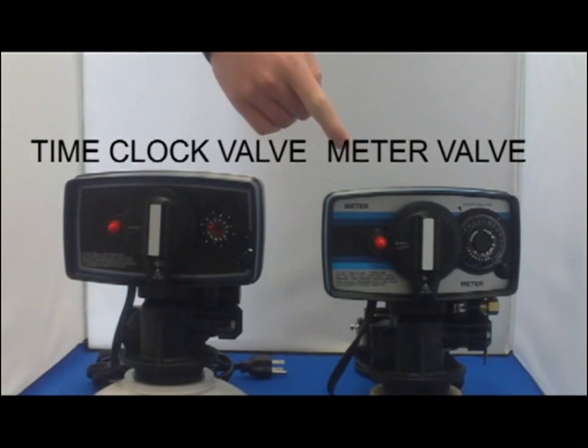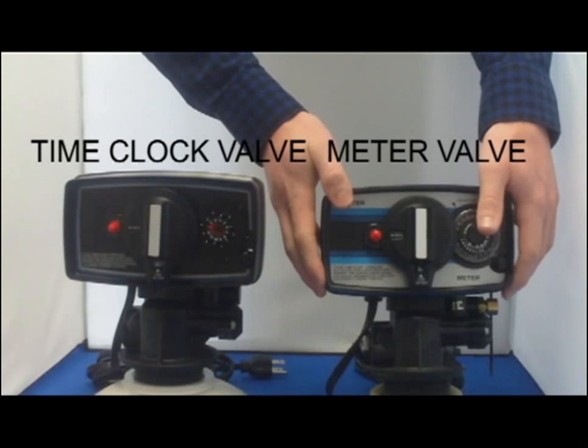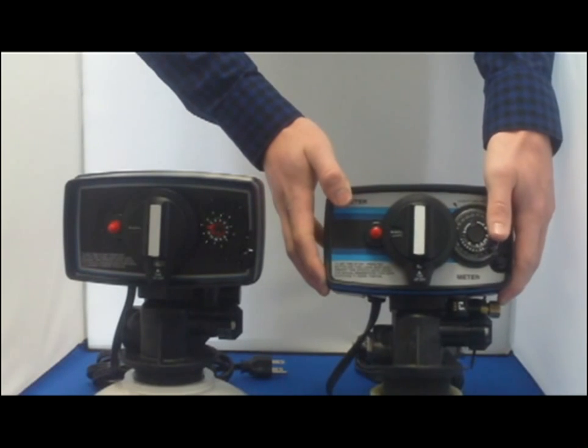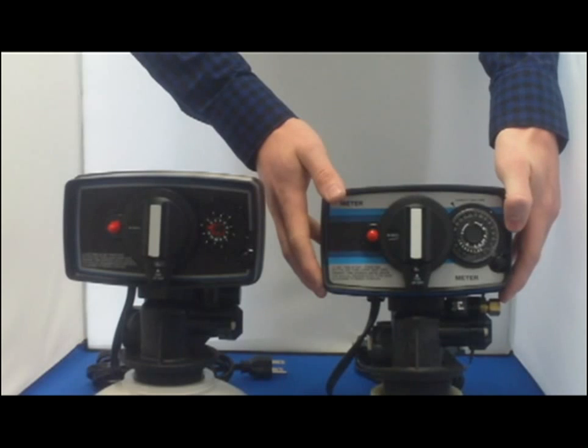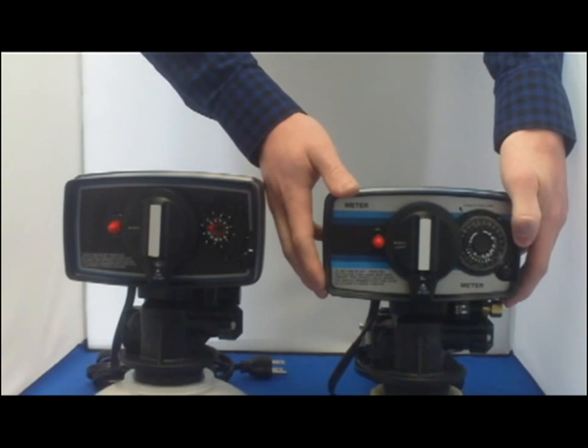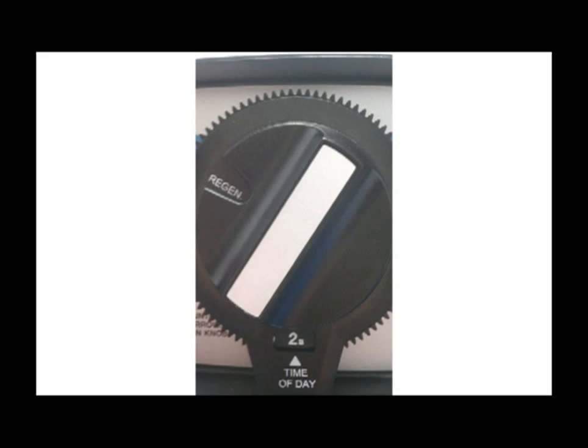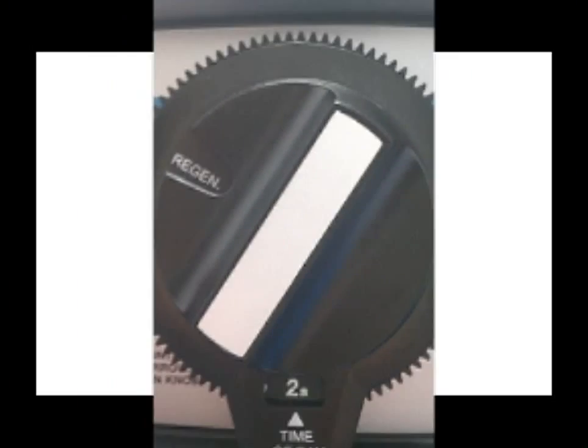First let's take a look at meter valves, also called volume initiated valves. These types of valves count gallons of water passing through the system. When the programmed volume of water has been used, the system will automatically regenerate itself at 2 a.m. unless the default settings have been altered.